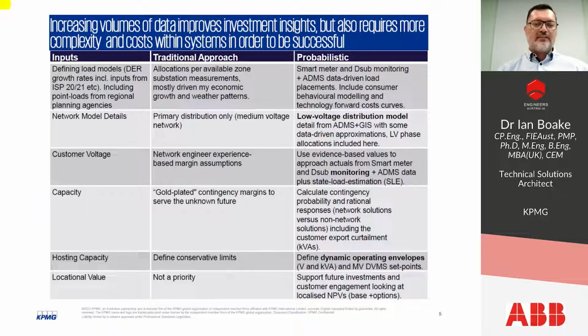So we've mentioned hosting capacity. The networks do manage their voltages, but they are pretty limited in terms of tapping up and tapping down the zone transformer, in terms of many operations of the tap changer, and usually have fixed taps on the distribution substation. So it is a fairly complex problem from their perspective. It is a problem that scales to the tune of millions of consumers. So if they spend $1 per consumer, that quickly amounts to, say, $1 million in OPEX per year.